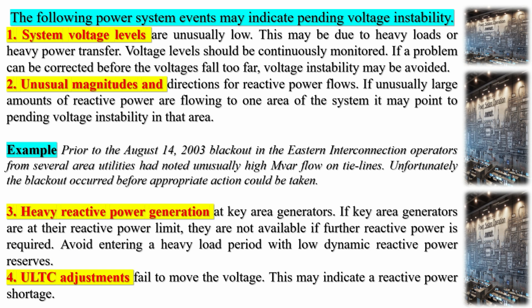System voltage levels are unusually low. This may be due to heavy loads or heavy power transfer. Voltage levels should be continuously monitored. If a problem can be corrected before the voltages fall too far, voltage instability may be avoided. Unusual magnitudes and directions for reactive power flows. If unusually large amounts of reactive power are flowing to one area of the system, it may point to pending voltage instability in that area. Best example is the August 14, 2003 blackout in the Eastern Interconnection in the USA, where operators from several area utilities had noted unusually high VAR flow on tie lines. Unfortunately, the blackout occurred before appropriate action could be taken.